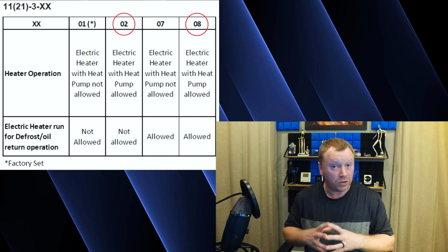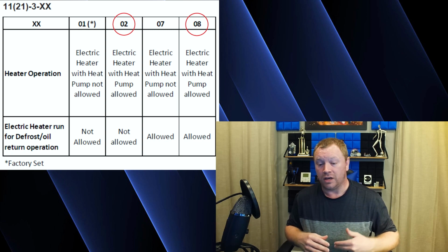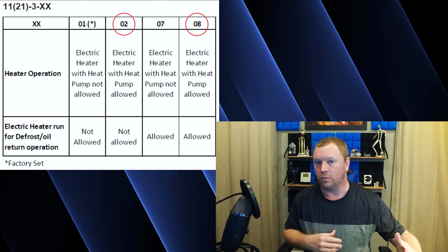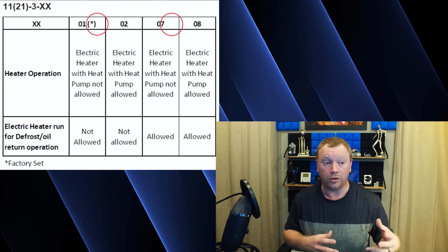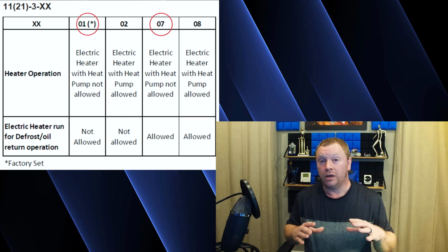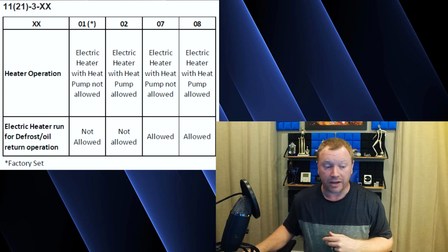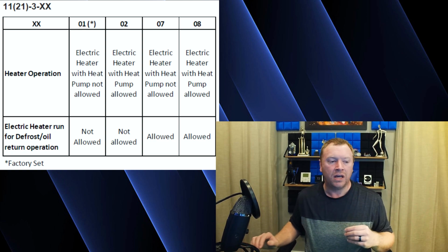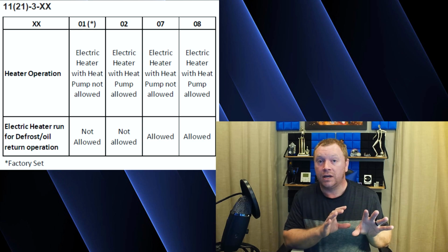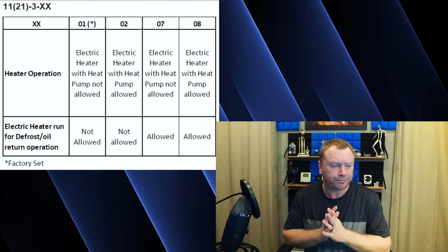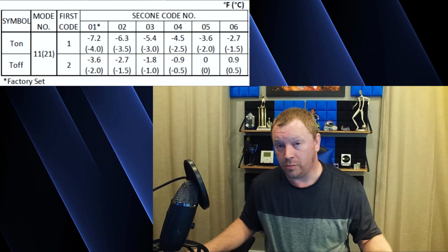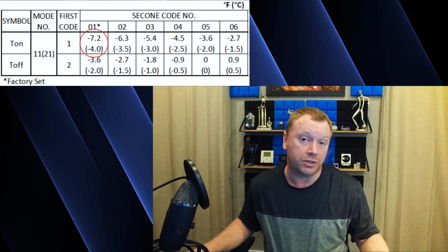pump. Then what you also need to set is the T on, T off. If you decide, no, I'm not going to run the strip heat with the heat pump, option 3-01 or 3-07, it's not allowed, then you don't need to program T on, T off. So let's say, yeah, you are going to program the strip heat to run with the heat pump as a supplemental heating, just in case the heat pump doesn't keep up for whatever reason. Something happens and it's falling behind. Okay, well, before you program T on, T off, you need to have a conversation with the end user, because your T on temperature cannot go any lower than 7.2 degrees.